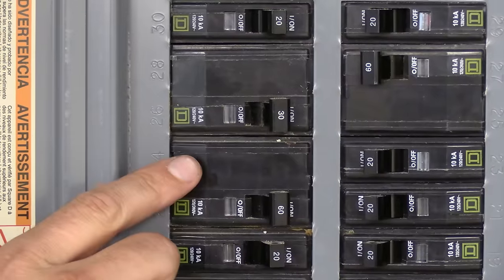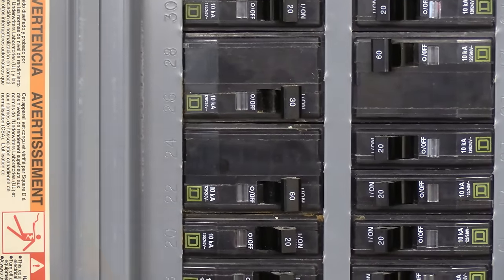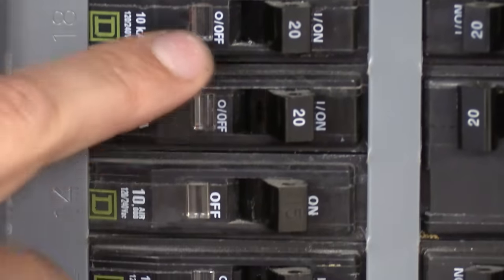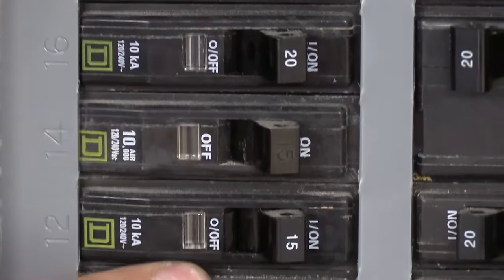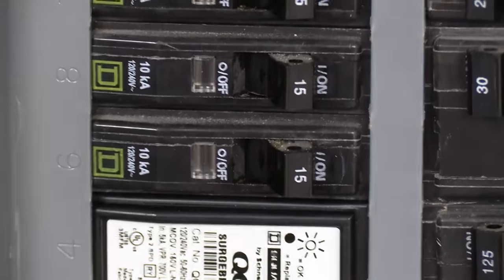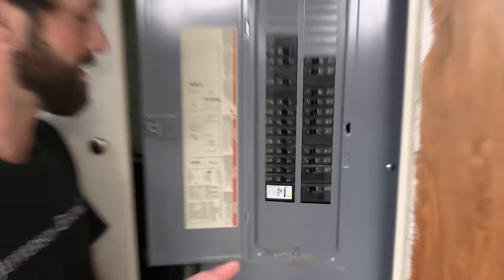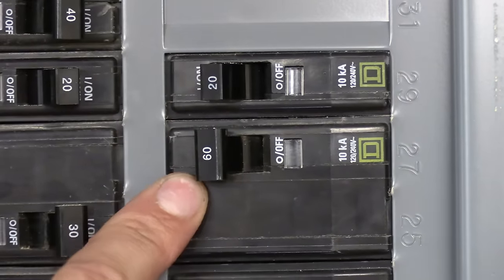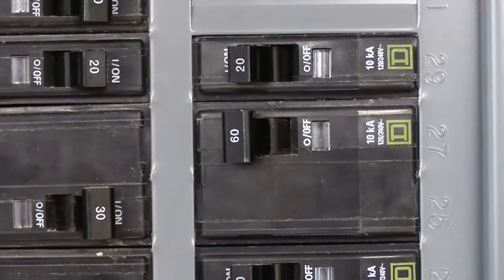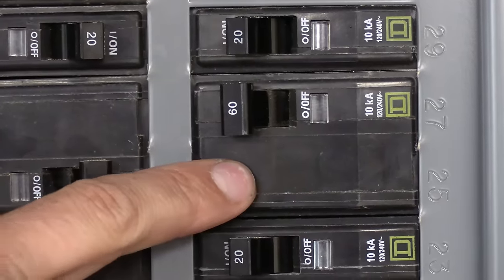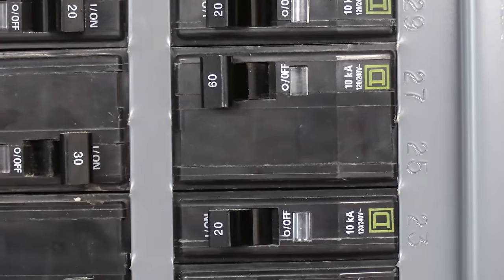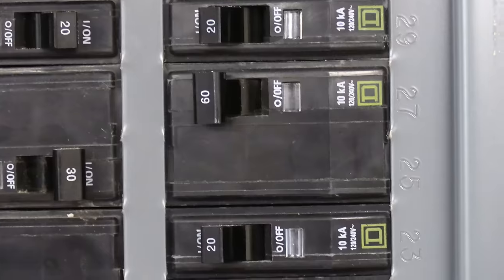Typically, air conditioners are going to fall within the 20 to 60 amp range. Now I've got some more 20 amp circuits here. That's likely going to be kitchen and bathroom power. There's a 15, 15, 15. That's probably going to be general use lights and outlets like bedrooms, living rooms, et cetera. Here I've got a two pole 60 amp breaker and it's labeled kitchen sub, sub for sub panel. So that's going to be a distinct panel that's being fed off of this and going to contain circuits of its own.